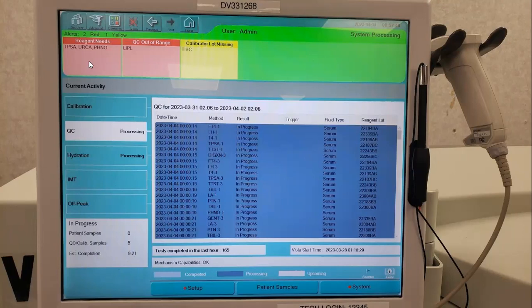And already it has reagent needs, so either I did not pull off these flex packs, and they are out now, or the machine did not want to run them on expired packs and discarded them. If a QC level is out of range, it will pop up QC out of range in a red box. This is one that we will have to rerun. I will wait until everything has ran to see what we need to rerun.